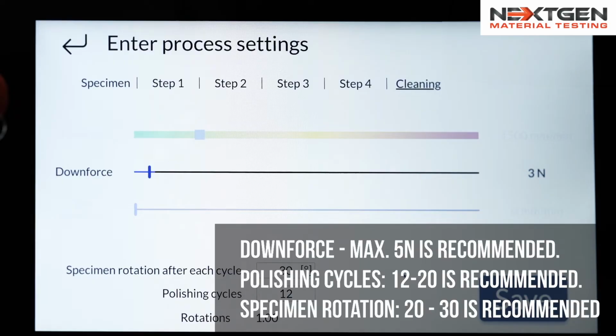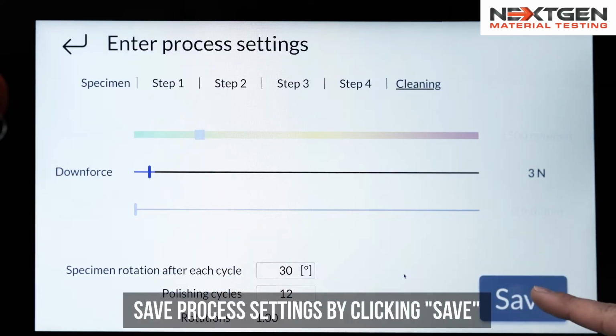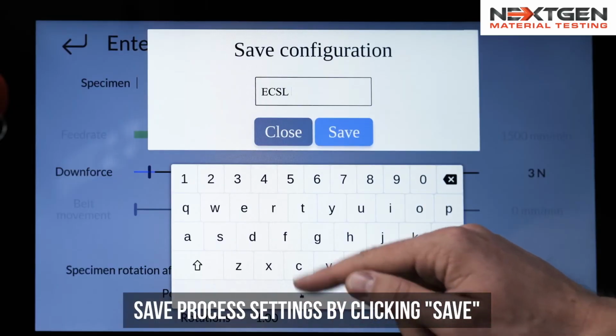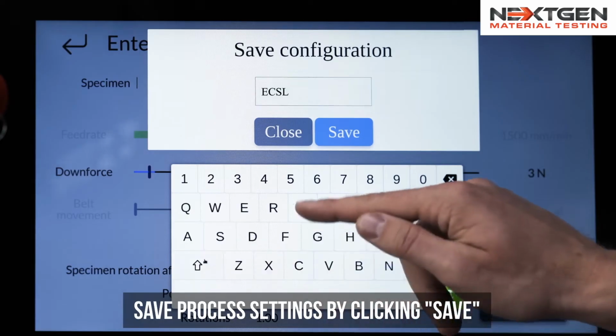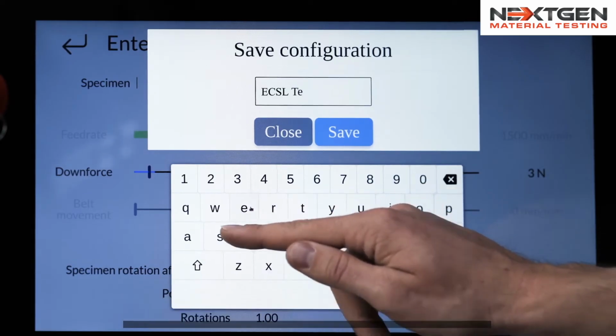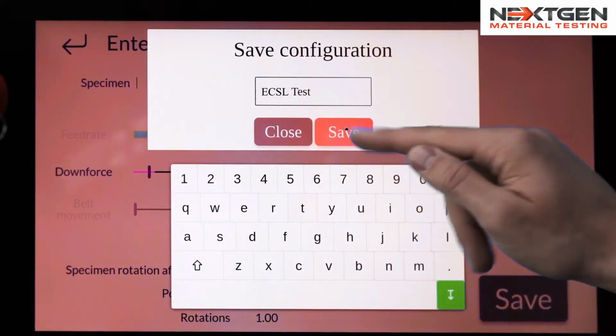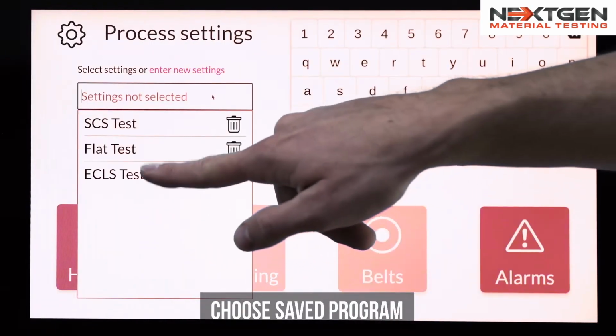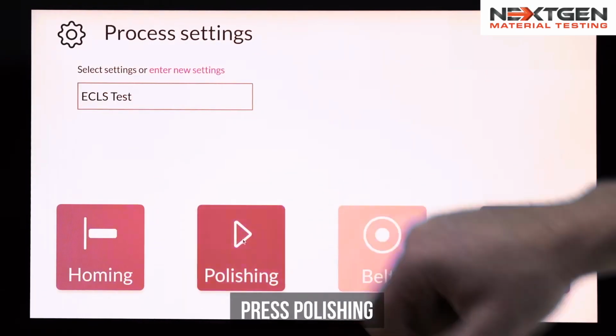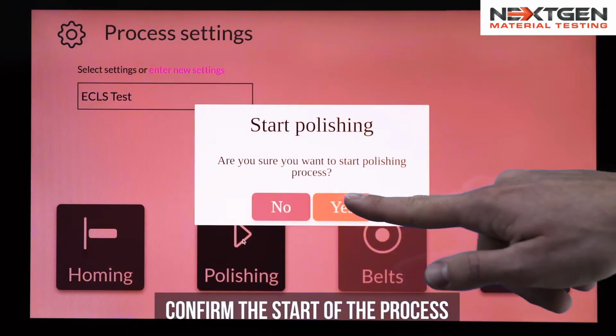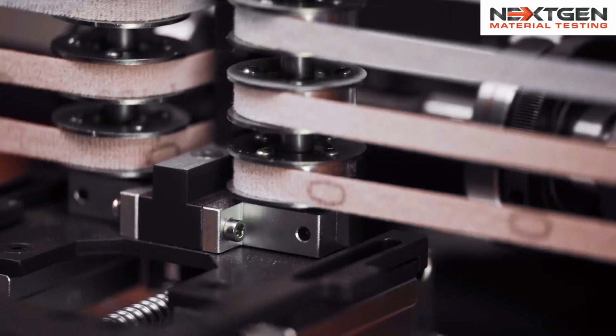Recommended downforce, maximum, 5N. Recommended polishing cycles, 12 to 20. Recommended rotation, 20 to 30 degrees. Save the process by selecting Save. Load the saved program. Press Polishing. Confirm the process start.